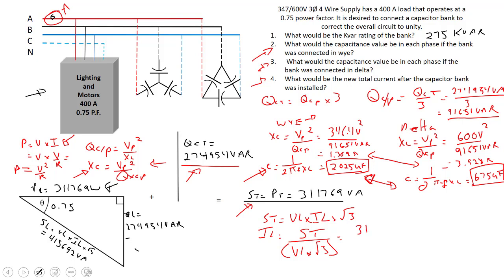If I put those numbers in: 311,769 VA divided by 600 volt times root 3, we're going to get approximately 300 amps.